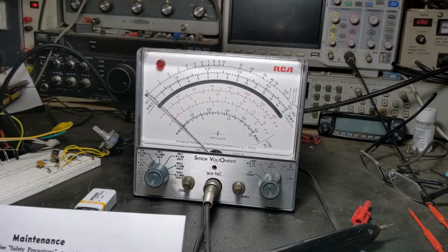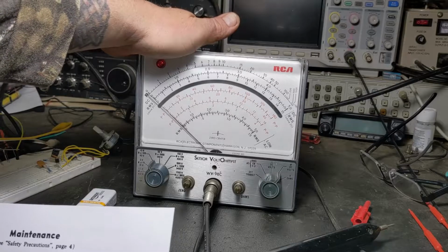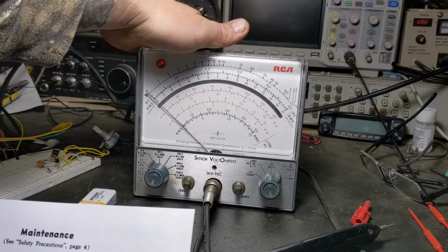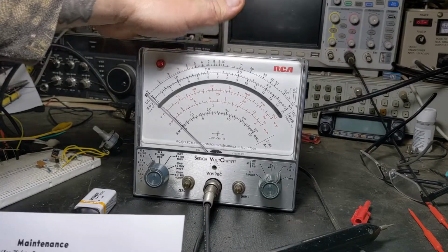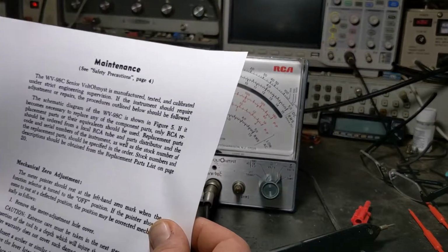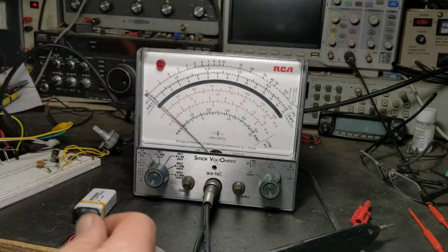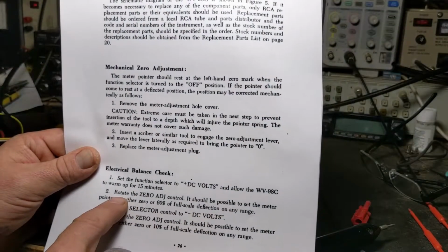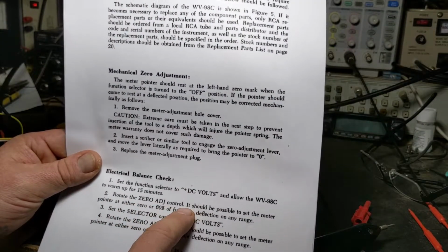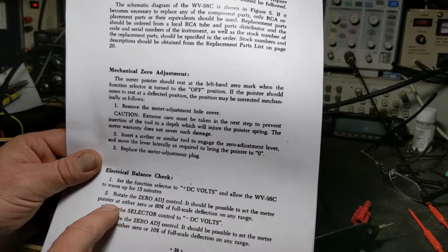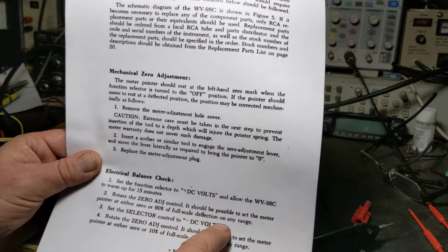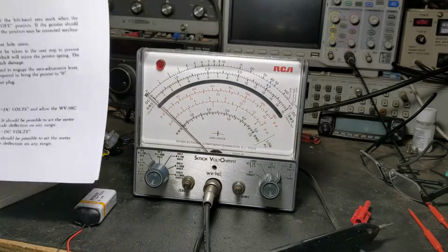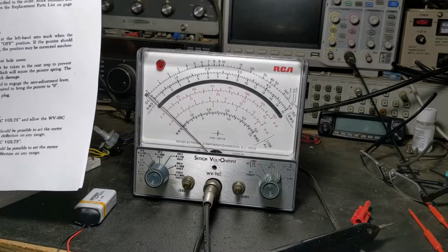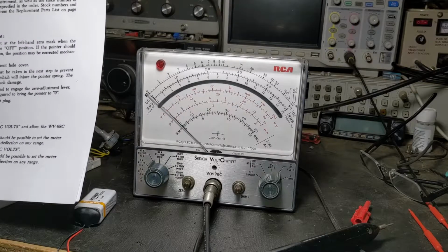That's on, it's just I ain't got the case on, you can't see that hardly. You probably, if I do, yeah, so you can see if I do that. But that neon indicator is working. But it says here, rotate the 0 adjustment control. It should be possible to set the meter pointer at either 0 or 60% of full deflection on any range. Well, I think I'm double reading here or something.